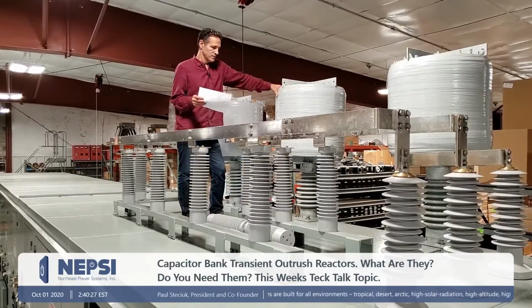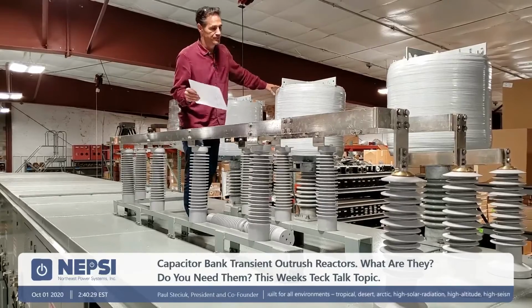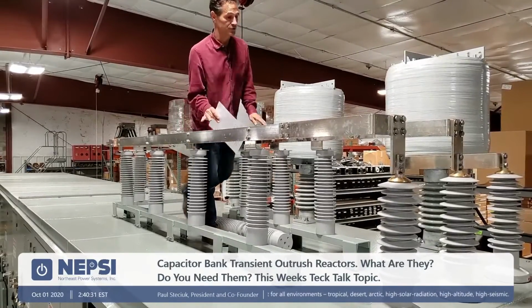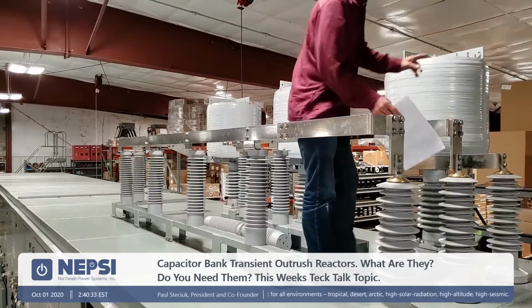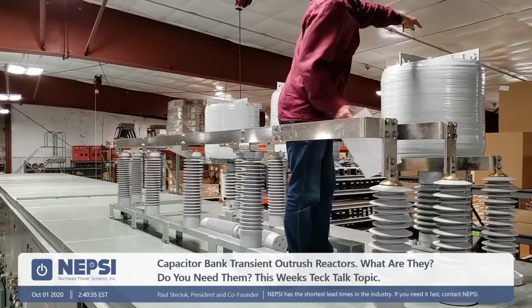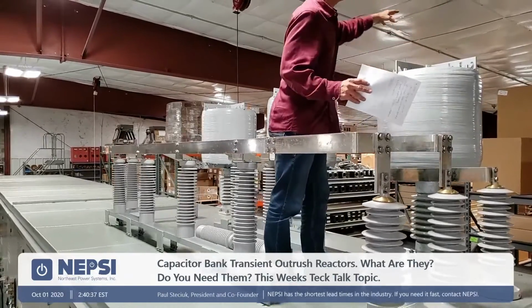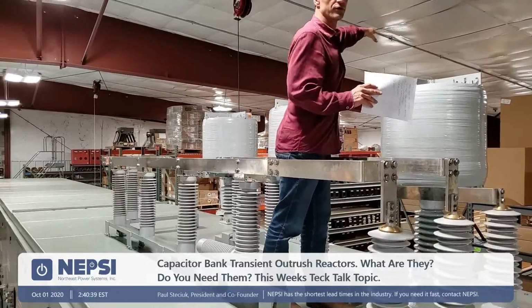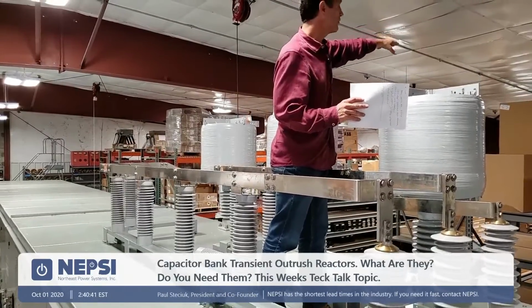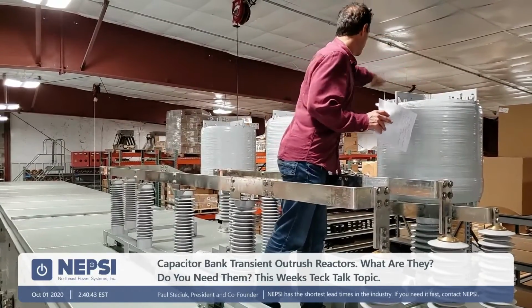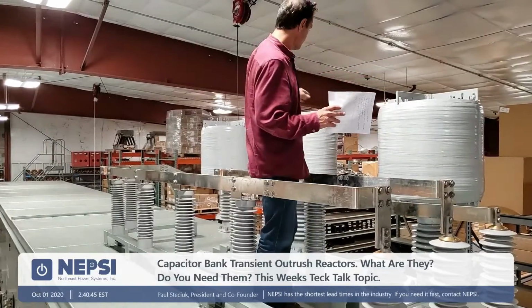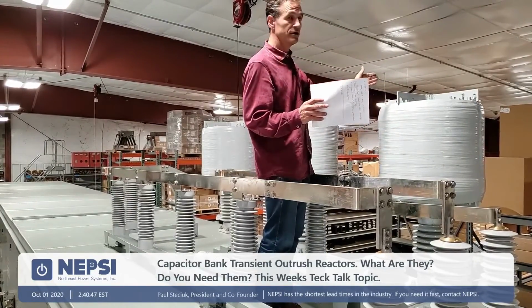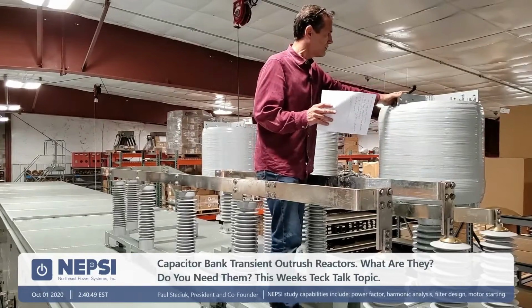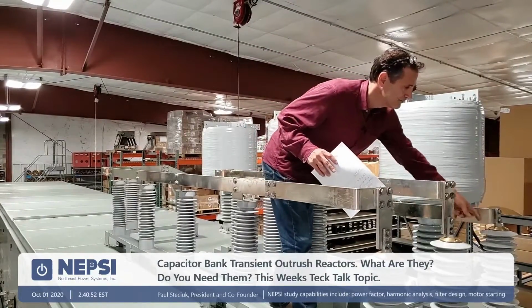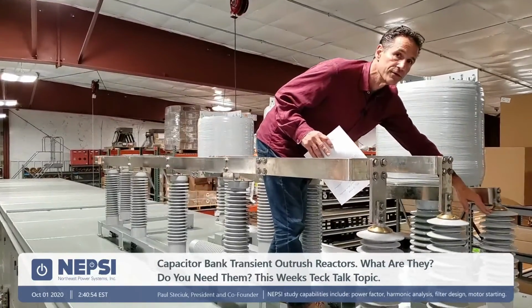So let's just talk about the customer connection point first. In this case, the customer is connecting to the terminals on the outside here. They actually have their bus work over here associated with their substation network, and they're going to cable down to these three reactors. So you've got a phase A, B, and C set of reactors. Those reactors are bussed into these bushings here.